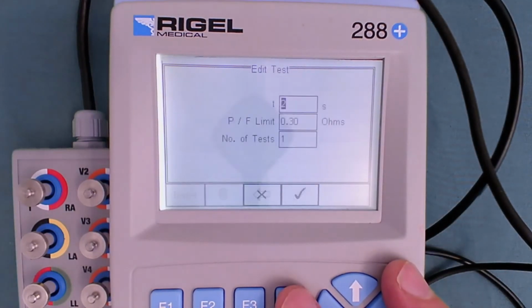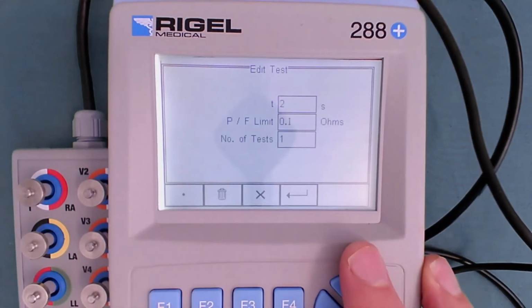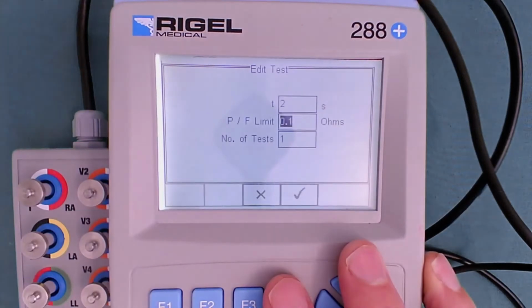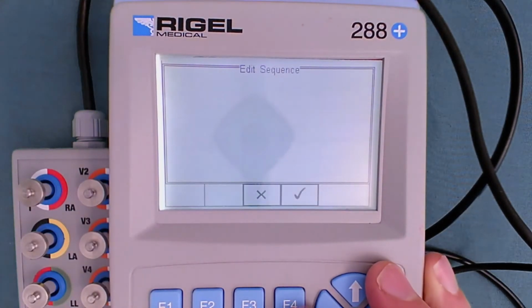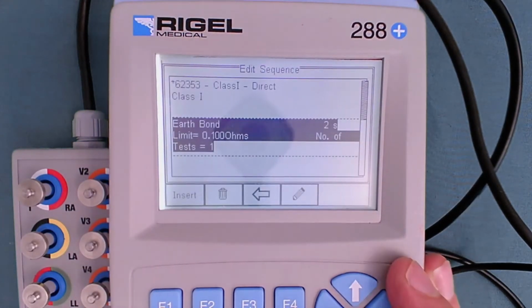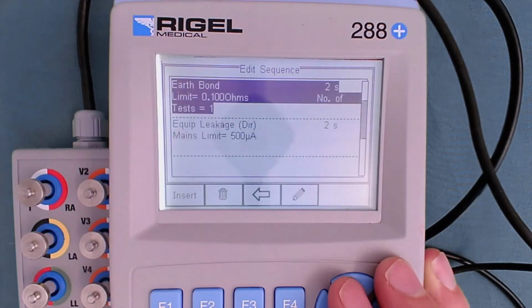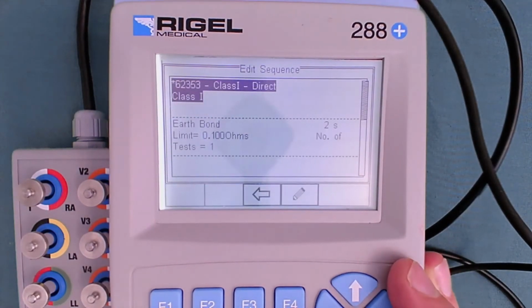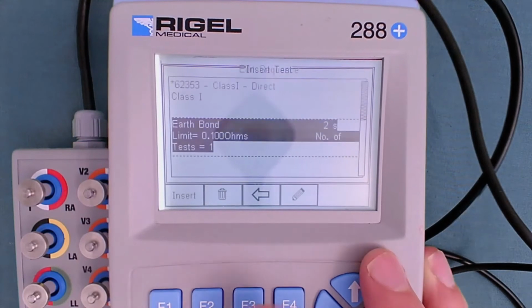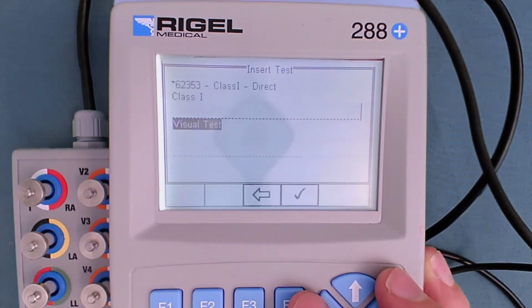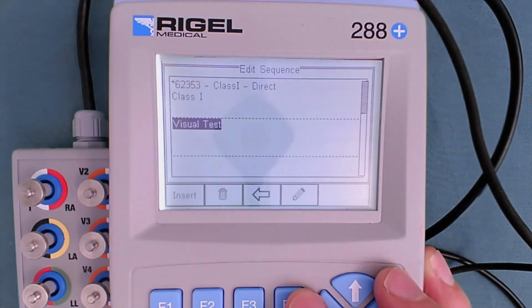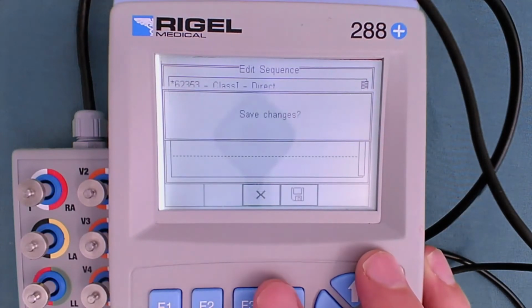So we can edit the earth bond test, we can change the pass-fail limit for the resistance measurement. You can change the time, duration, etc. But you can also insert tests. So you can insert individual tests. So let's put it before earth bond. Let's add a visual test as part of our procedure. Press F3 and save the changes.